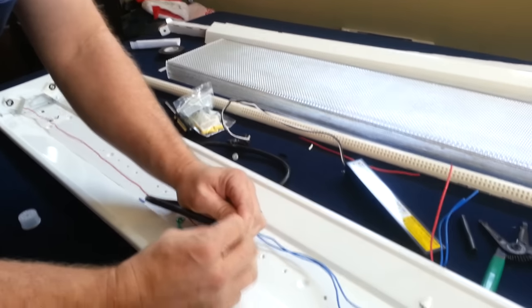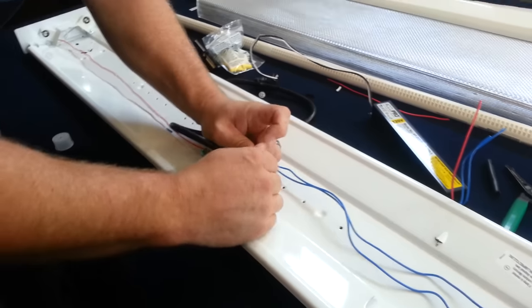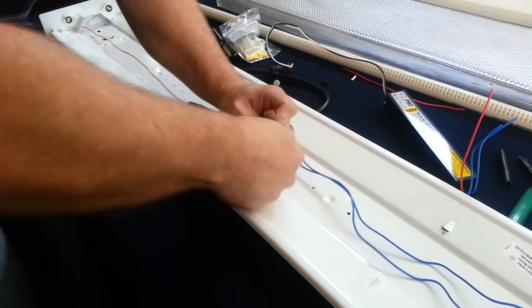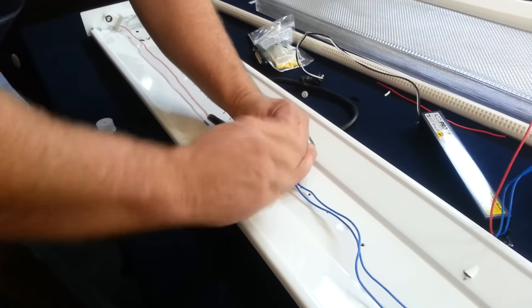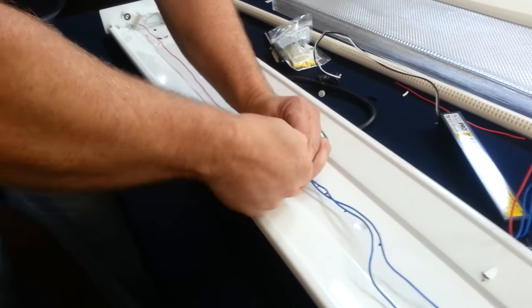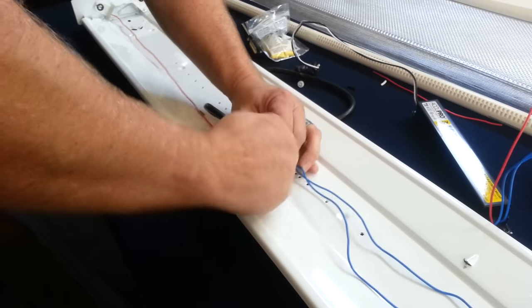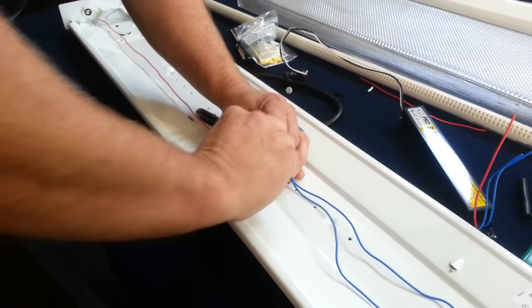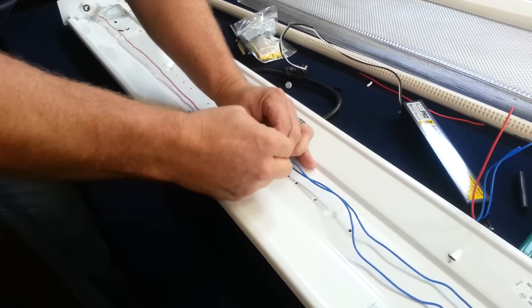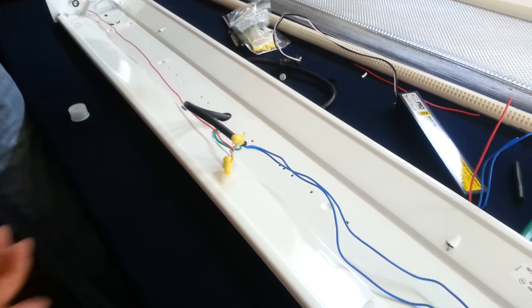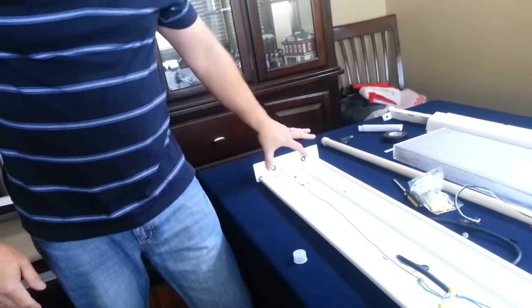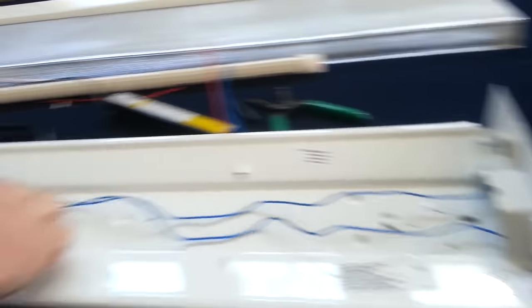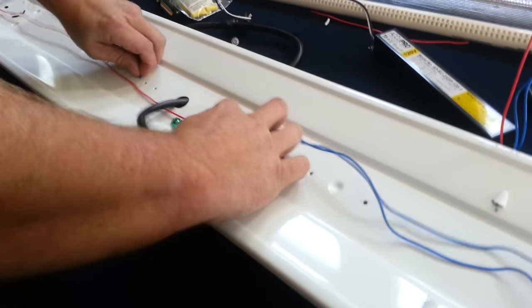Remember to leave your stranded wire a little bit above your solids. Grab yourself another wire nut and start twisting. Remember, give yourself that one and a half inches of pigtail. Now you've got it firmly tight and it won't be pulled out. Give it a tug, make sure everything's solid. Once you've got it wired like that, all you've done is bypass the ballast. We are directly running hot wire that goes to one side of the tombstones and the neutral wire goes to the other. We've just bypassed the ballast.